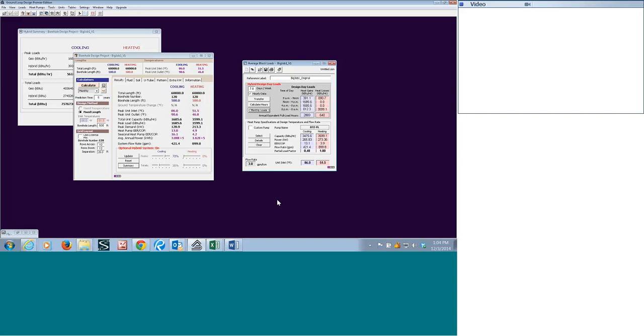Thank you, Terry. That's very helpful. It certainly reinforces our experience. We designed the borehole thermal energy storage in Okotoks, Alberta, for the subdivision of houses that's heated from heat that we collect in the summer and store away in a borehole field for the winter, and it's probably the biggest of its type around, and you've got to do absolutely everything possible to insulate that borehole field from the rest of the world, and we recover only 50% of the solar energy that we pack in there in the summer to get it out in the winter. So absolutely, Earth is not a good storage medium. It conducts... I was just going to say that.